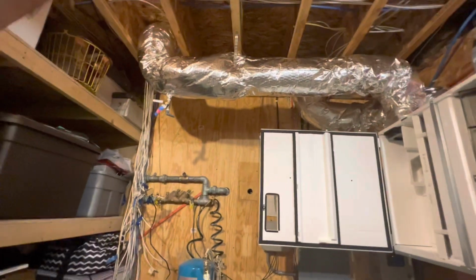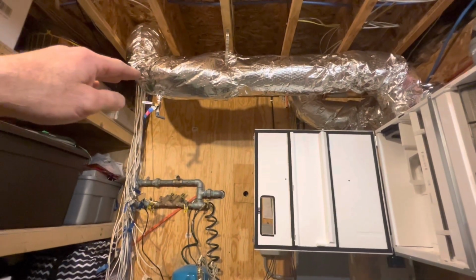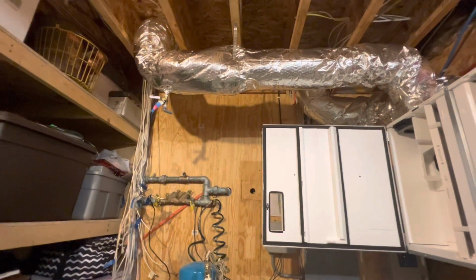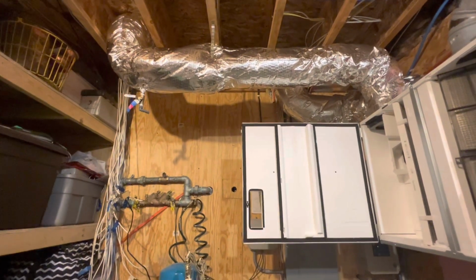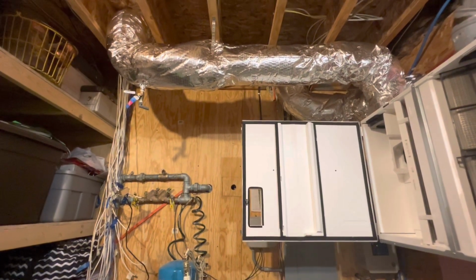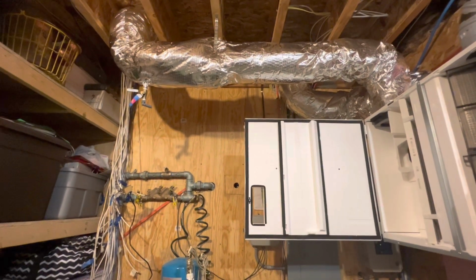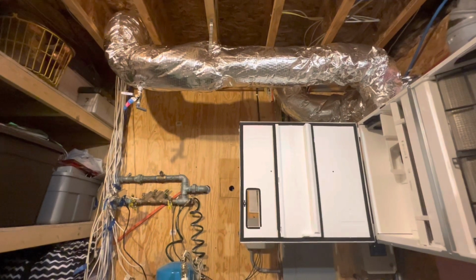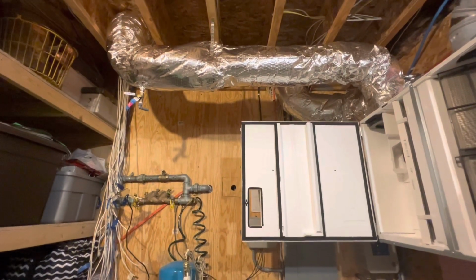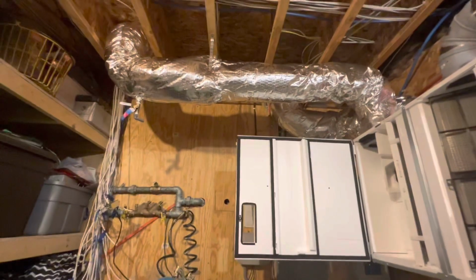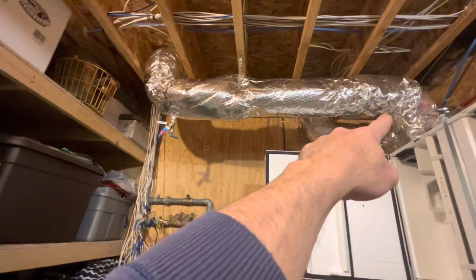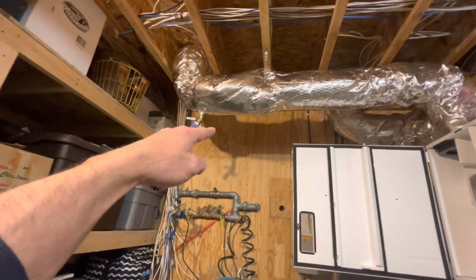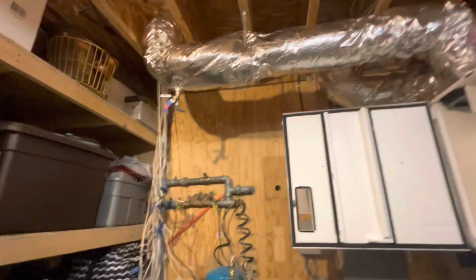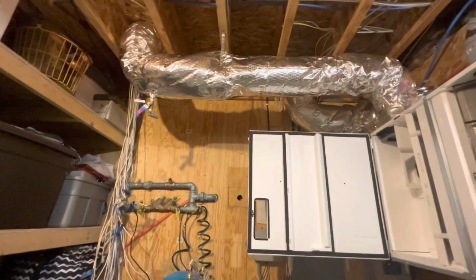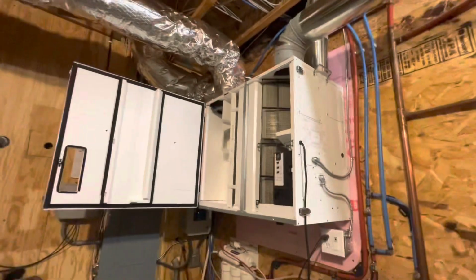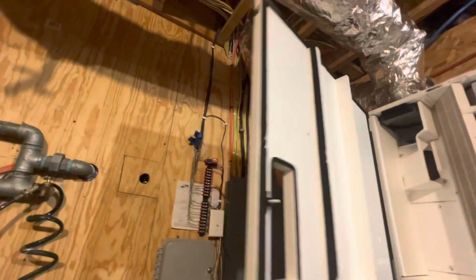So for my cold side ductwork, just the way my house is laid out and where I had to install it, I was worried about condensation building up in the lines since they go vertical on the outside of the house. In the summertime, if condensation builds up in those lines or any moisture gets in, I wouldn't have any way for it to get out before it dumped into the ERV. So I have this line from that elbow over to this drain line sloped down towards the valve, and my thought was that I would install drain loops off of that valve, have a water leg, and then run it over to a floor drain. And I have the same thing for the other line as well.